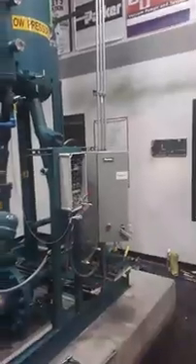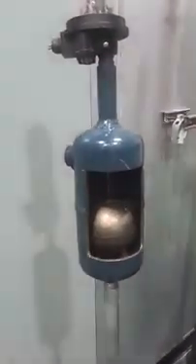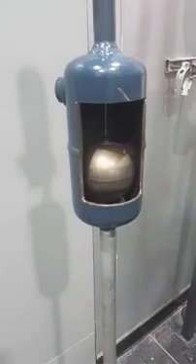Let me reverse the camera and talk about testing high level floats. This right here is an example of a high level float — what you see is a cutaway. I'm going to put my finger where the mechanical ball is on the inside — it's a buoyancy ball. On top we have closing contacts, and this whole top portion slides off. You have a rod that continues up, and the stem is able to go up in there.